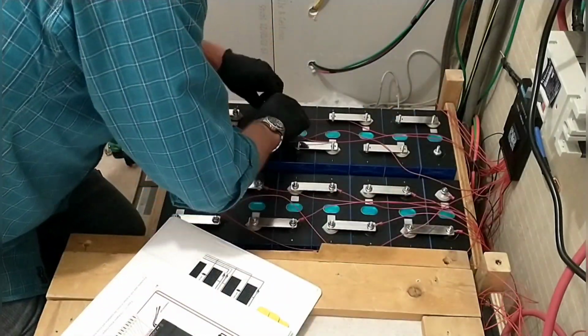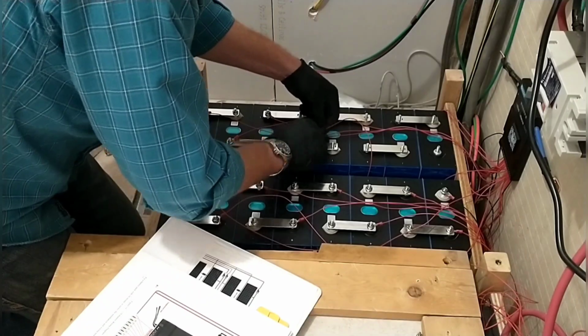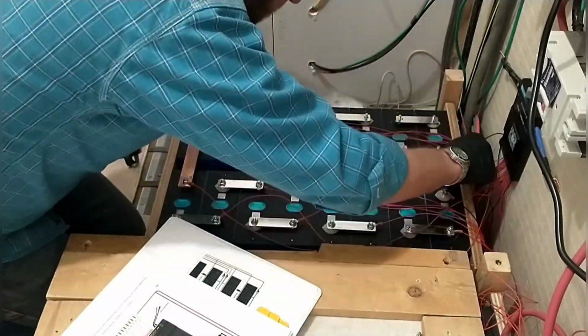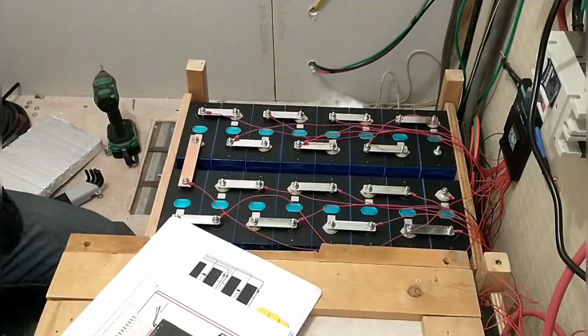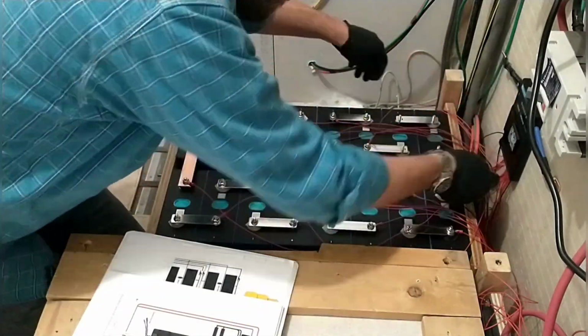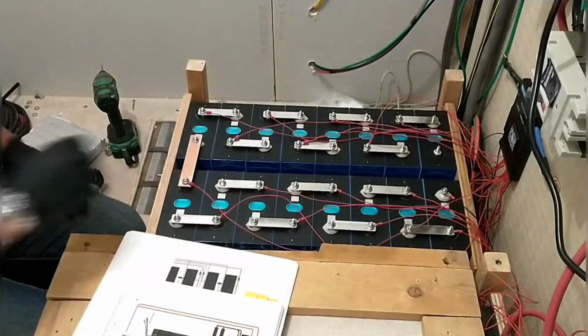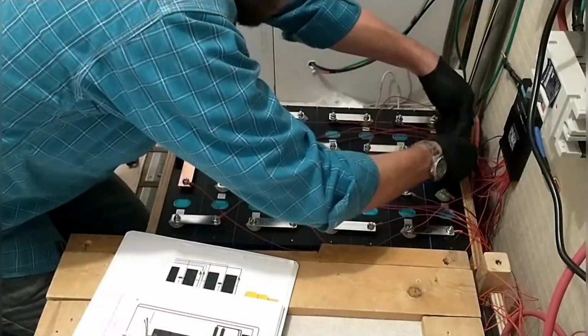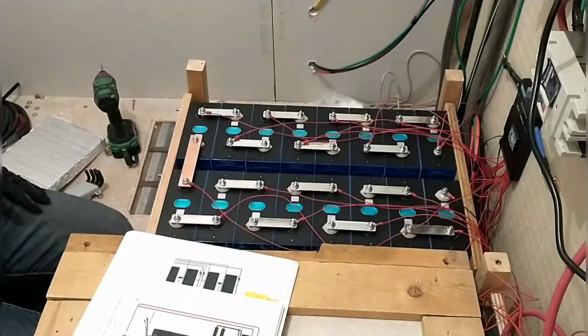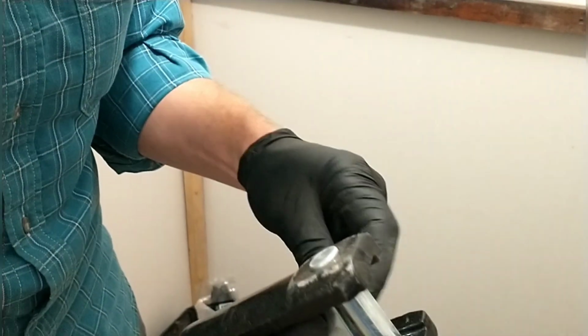It has an active balancing feature where it can send up to 2 amps of power to individual cells to equalize the power between them, and that balancing gives a lot more longevity to the battery. It will also fault if one of the cells goes bad and shut down the system so I can replace the individual cells, so it's an invaluable component in this system.